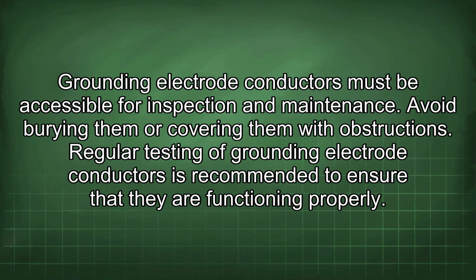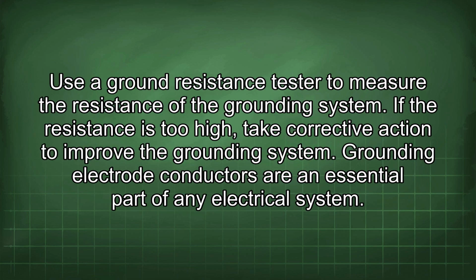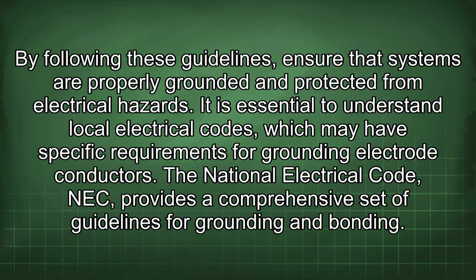Regular testing of grounding electrode conductors is recommended to ensure that they are functioning properly. Use a ground resistance tester to measure the resistance of the grounding system. If the resistance is too high, take corrective action to improve the grounding system. Grounding electrode conductors are an essential part of any electrical system. By following these guidelines, ensure that systems are properly grounded and protected from electrical hazards.